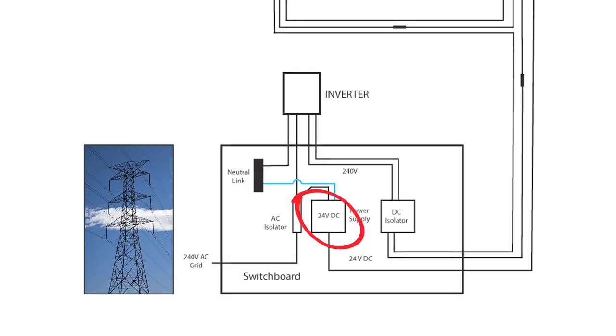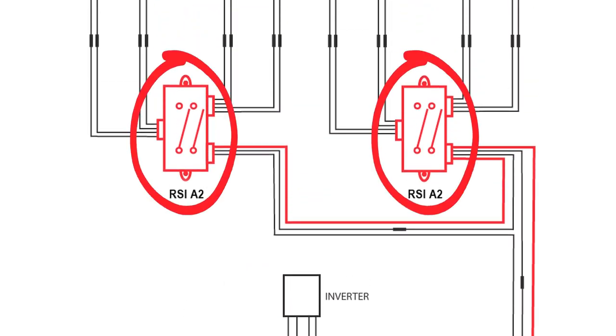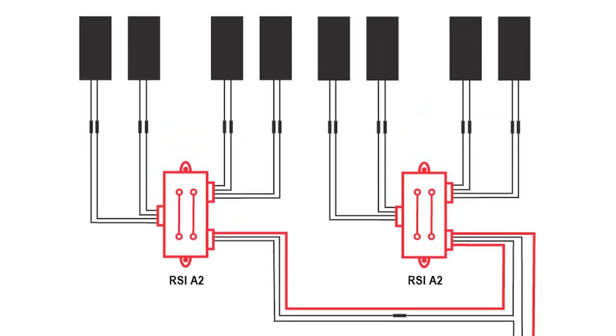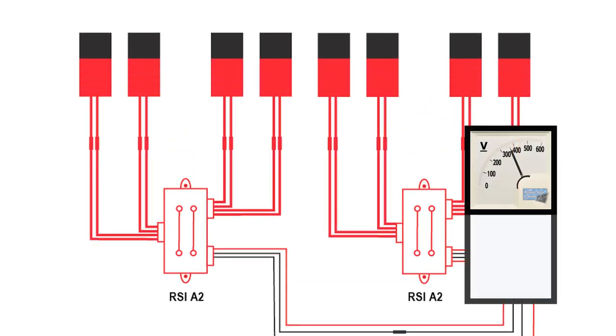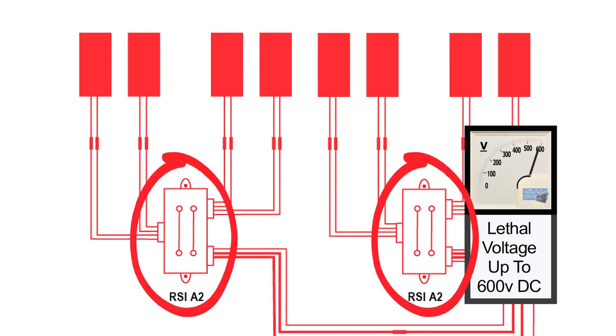A 24 volt DC power supply is energized from the grid AC supply. This then supplies the required power to the RSI, which in turn closes the desired contacts. This will then allow all connected solar panels to combine their voltage and supply DC volts to the inverter. The contacts continuously remain in the combining position until their supply is interrupted.